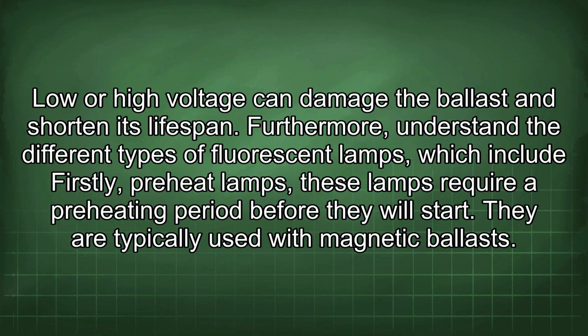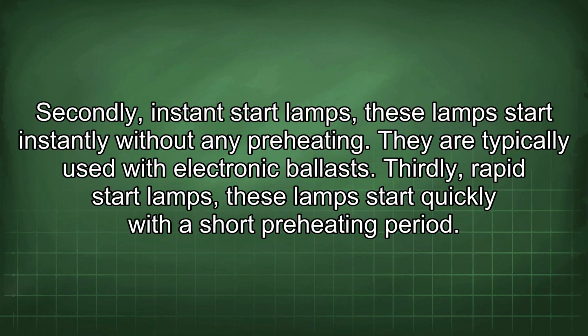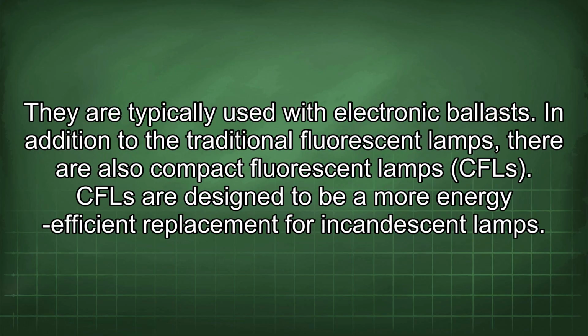Furthermore, understand the different types of fluorescent lamps, which include, firstly, preheat lamps. These lamps require a preheating period before they will start. They are typically used with magnetic ballasts. Secondly, instant start lamps. These lamps start instantly without any preheating. They are typically used with electronic ballasts. Thirdly, rapid start lamps. These lamps start quickly with a short preheating period. They are typically used with electronic ballasts.